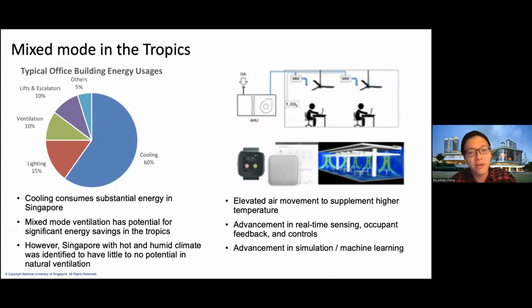The hybrid system has become increasingly used in Singapore. Basically, we provide an elevated temperature to save energy and reduce demand. So instead of a typical set point of 23 or 24 in the tropics, we have 26 or 27 degrees Celsius. How we still achieve comfort is through elevated air movement from ceiling fans.